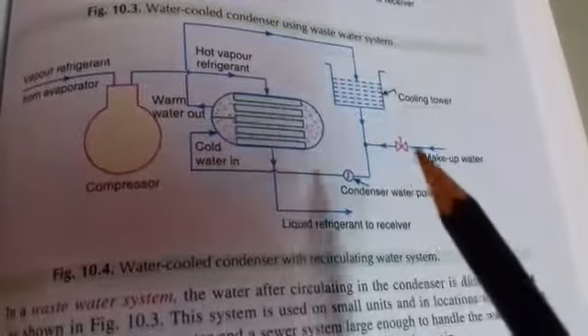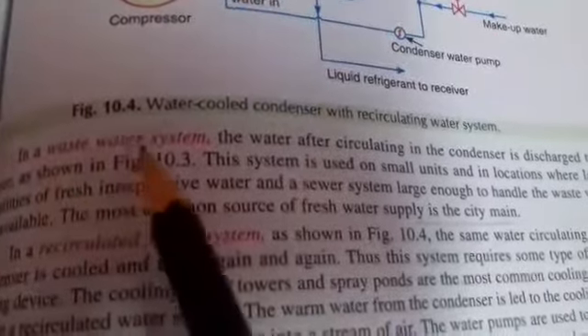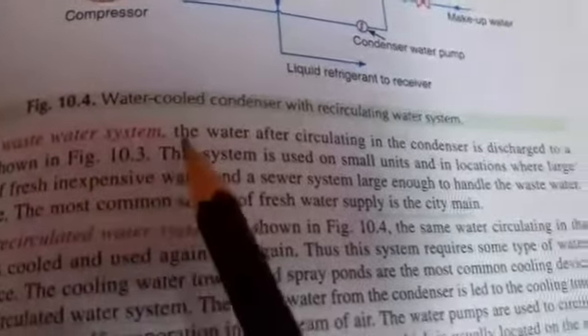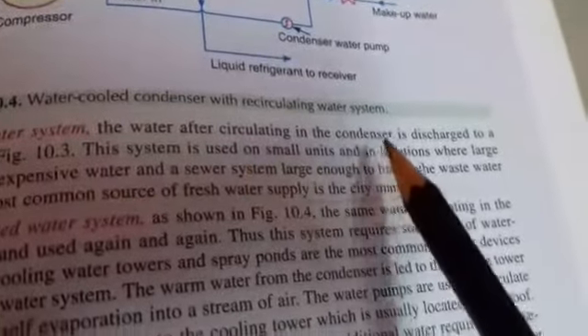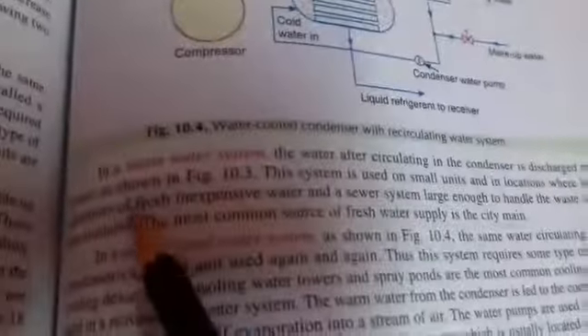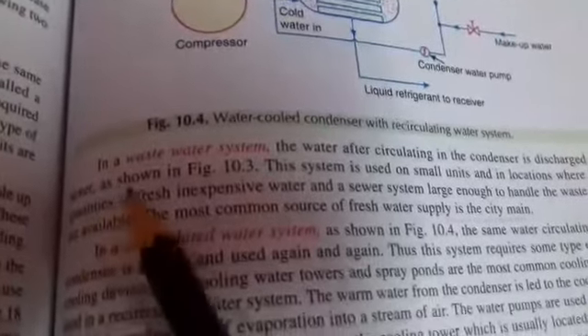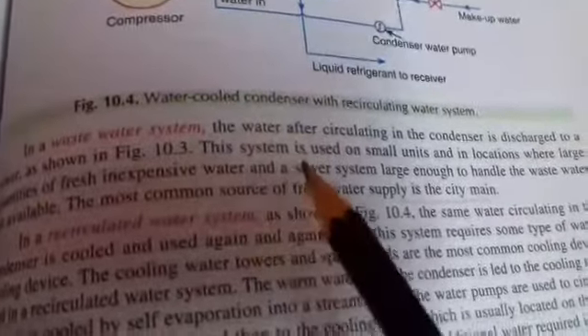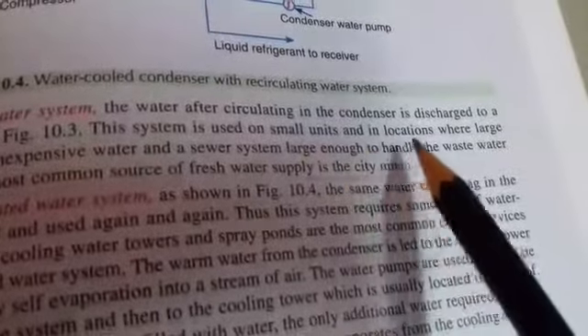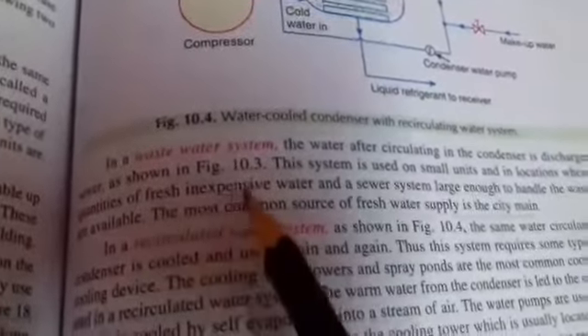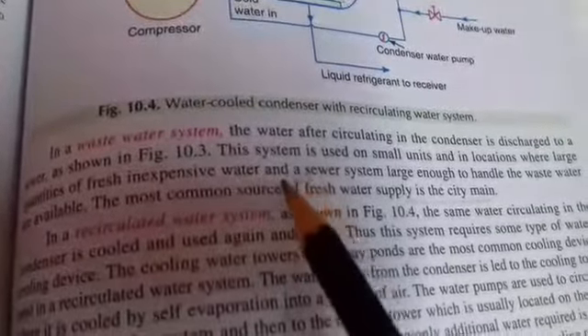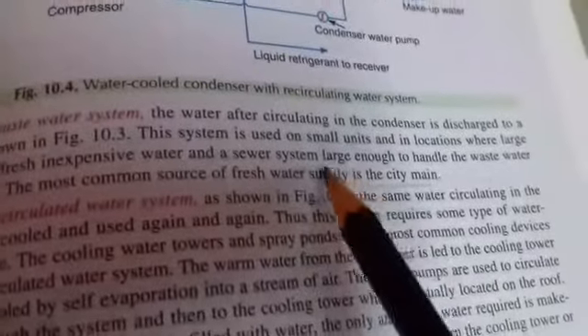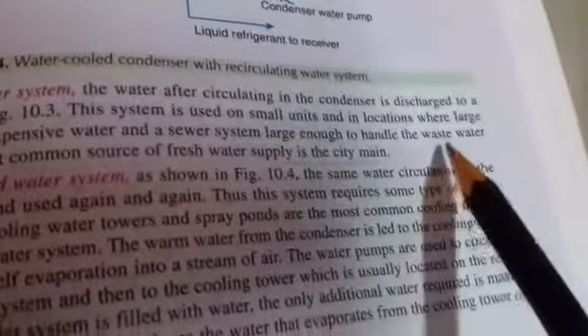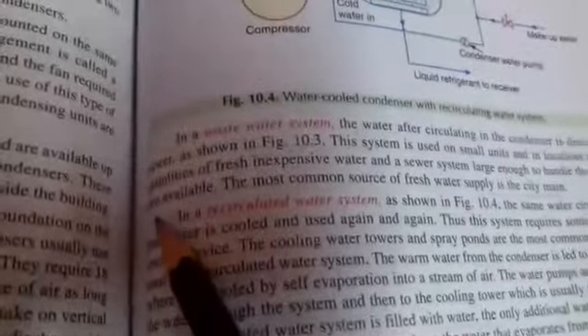Second, in a wastewater system, the water after circulating in the condenser is discharged to sewer, as shown in the figure I have shown. This system is used on a small unit and in location where large quantity of fresh inexpensive water and a sewer system large enough to handle the waste water are available. The most common source of fresh water supply is the city main.